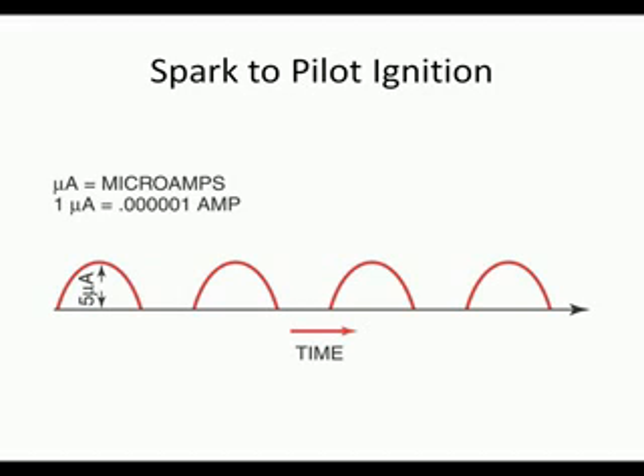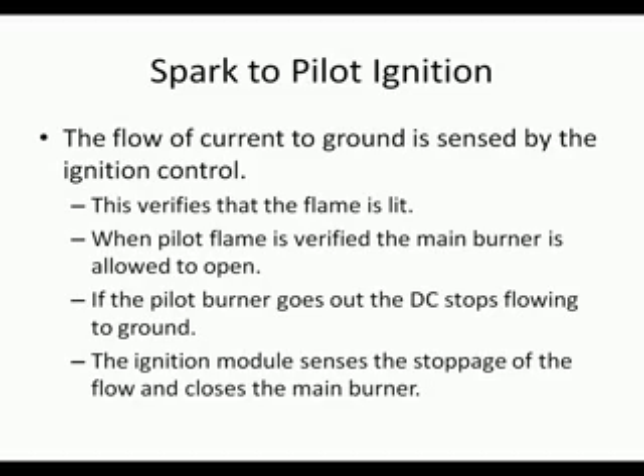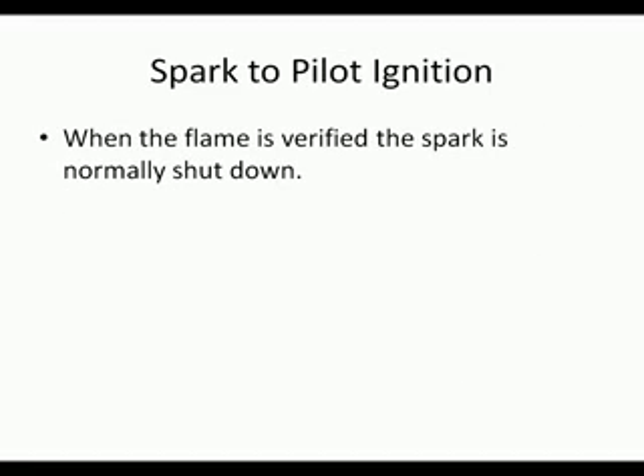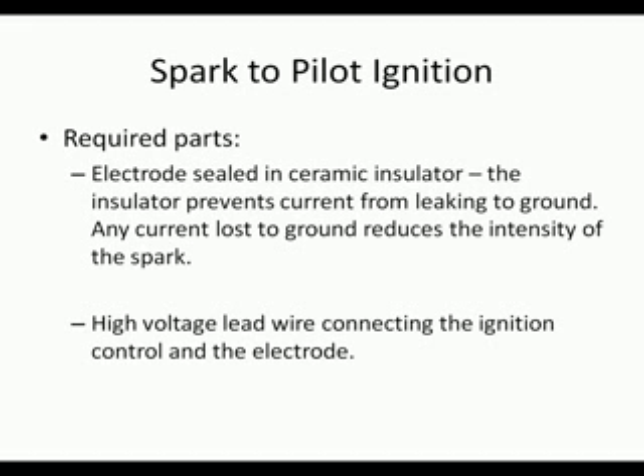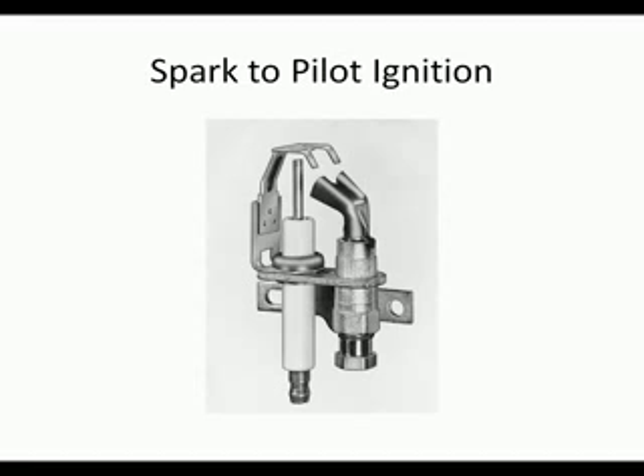So what we're doing is providing some current, which is an alternating current or AC sine wave, to the flame sensor. The flame sensor, which is in the pilot flame, allows only half of that AC current to pass. The flow of current to ground is sensed by the ignition control. It verifies that the flame is lit. When the pilot flame is verified, the main burner is allowed to open, and if the pilot goes out, the DC current stops flowing to ground. The ignition module senses the stoppage of the flow and closes the main burner, thus preventing unburnt gas from spilling into the space. When the flame is verified in a spark-to-pilot system, the spark is normally shut down.